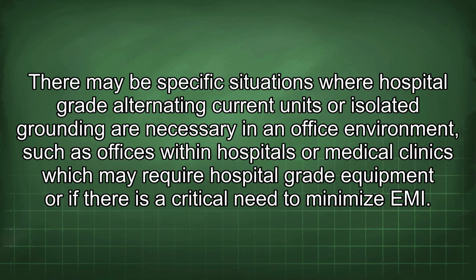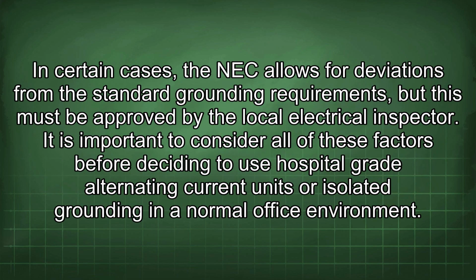There may be specific situations where hospital-grade alternating current units or isolated grounding are necessary in an office environment, such as offices within hospitals or medical clinics which may require hospital-grade equipment, or if there is a critical need to minimize EMI. In certain cases, the NEC allows for deviations from the standard grounding requirements, but this must be approved by the local electrical inspector. It is important to consider all of these factors before deciding to use hospital-grade alternating current units or isolated grounding in a normal office environment.